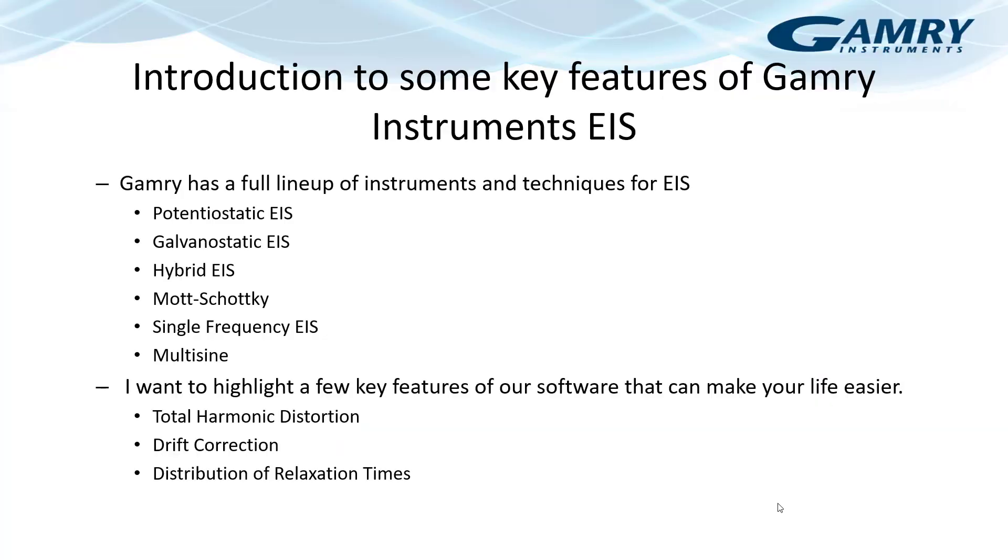So just very briefly here, as you would expect from most potentiostat manufacturers these days, we have a full lineup of instruments and techniques for impedance, that being potentiostatic EIS, galvanostatic EIS, hybrid EIS, which is a technique where we run galvanostatically but you get to input a cell voltage or an AC voltage that you want to maintain and we adjust the current level based on the current impedance that we've just measured. We also have Mott-Schottky single frequency EIS, so you could just measure a single frequency versus time, and of course we have multisine that can help you reduce your data acquisition time.